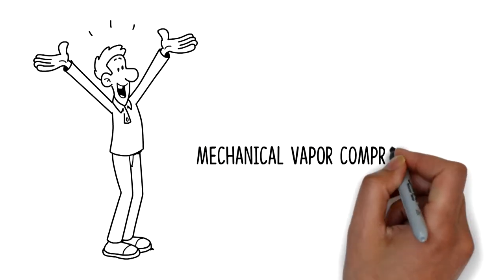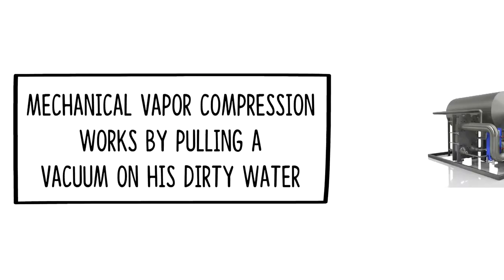Paul was happy to learn that mechanical vapor compression works by pulling a vacuum on his dirty water. The water boils and evaporates at a much lower temperature under vacuum.